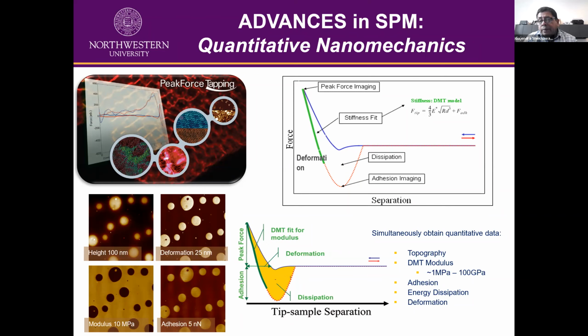intermittently brought together, similar to the tapping mode, to contact the surface, but for a short period, which eliminates the lateral forces, just like tapping. So unlike tapping mode, where the feedback loop keeps the cantilever vibration amplitude constant, peak force tapping basically controls the maximum force. That's called the peak force on the probe. So this process prevents the tip from damaging the sample.